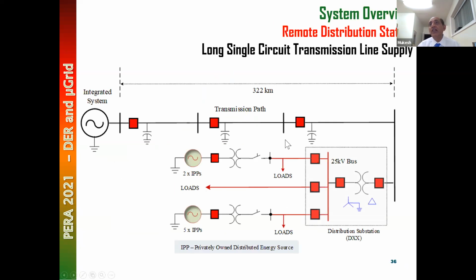The system is, again, like before, a transmission system. It is an integrated BC Hydro system supplying, through a very long 320-kilometer 130 kV transmission line, a small distribution station. It's a 25 kV distribution station, delta high side, Y grounded, and has three overhead feeders. Each of these feeders is very long. And as I said, over time, not for the reason of a microgrid, not for the reason of reliability of supply, but for other reasons, this is a very beautiful place with lots of rivers, and private investors came in with deregulation, and we got 7 run-of-the-river plants connected to this small location. 7 run-of-the-river plants, 7 privately owned. We call them IPPs, and they got connected to this small station for a period of time.